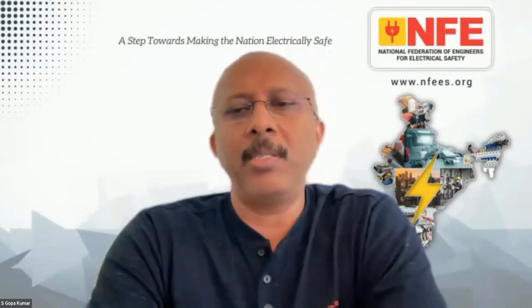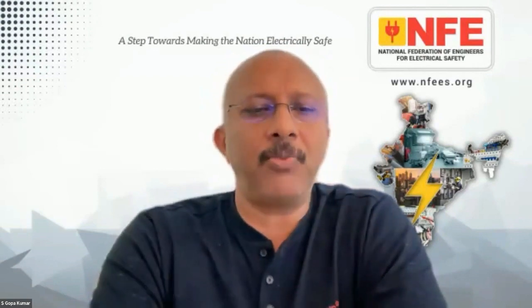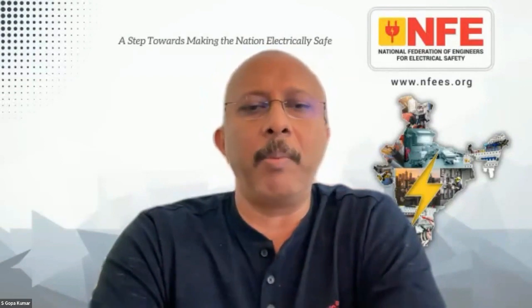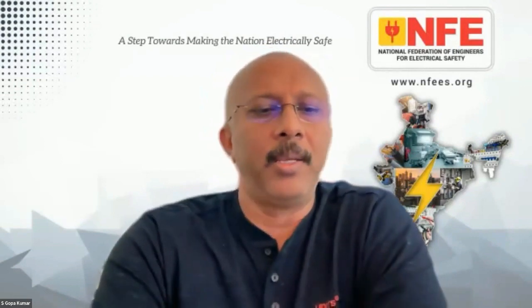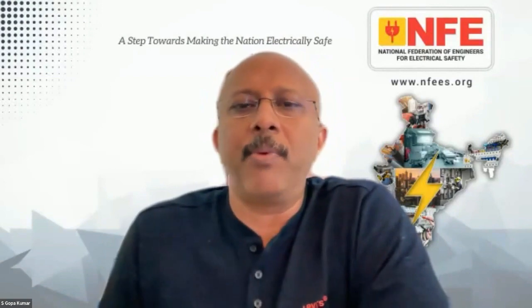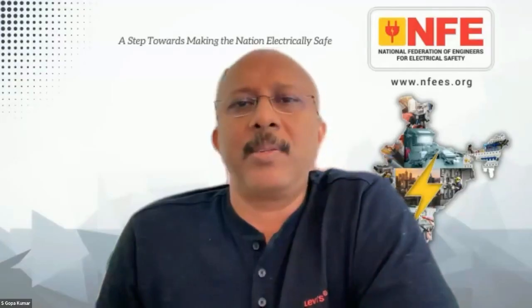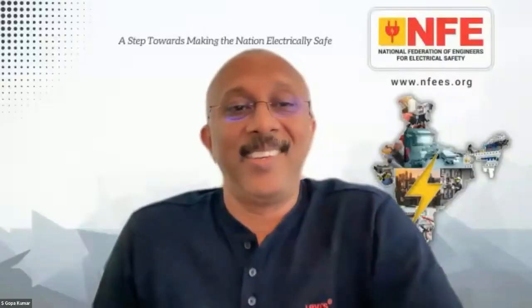But devices which use semiconductors or Y capacitors as filters will have more leakage current. But there are measures to handle it, and these are also explained very well in IS 732. We need to be mindful that all electronics now, in their natural performance, will leak to earth. So if you put a clamp meter on an earthing system, you will get natural leakage, and that can be perfectly healthy. It's when you try to disconnect an earth wire and it blows up in your face that you need to be mindful that there could be a problem. Hence, configuration is very important.